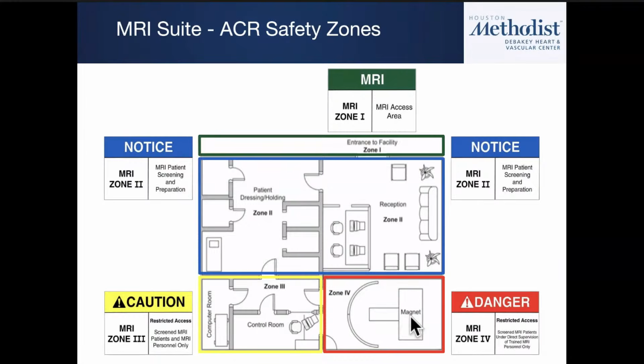Zone 3 becomes a much more controlled location, and typically there's a lock or a badge ID that you need to get into zone 3. Zone 3 is basically the control room, the area right next to zone 4, which is the actual magnet itself. The two areas you have to be very careful with are zone 3 and zone 4. Nobody should go into zone 3 until they've had metal screening done. And in zone 4, you should only have somebody when there's direct supervision. You can't take a patient, leave them on the table for 20 minutes and go grab a cup of coffee. They have to always be monitored by an MRI-trained person while somebody is inside zone 4.